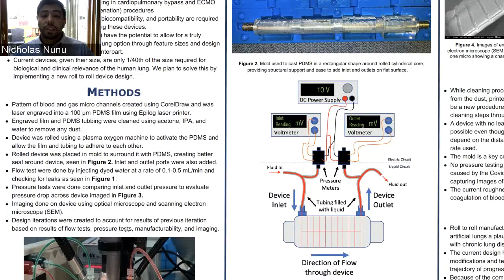So how our device works is we engrave a pattern of blood channels and gas channels to allow for blood and gas exchange in our device. And this pattern is laser printed onto a PDMS film that is about 100 microns thick. So it's a very thin film. The film is then rolled up onto a PDMS tubing substrate, and it's rolled up for several layers. So our device currently has about 4 layers, but we expect it to have anywhere up to 8 or 10.